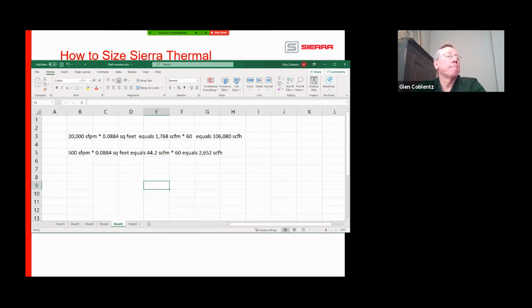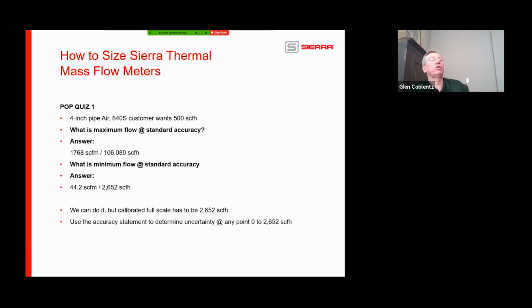Minimum flow, 500 times the area of the pipe, 44.2 SCFM, times 60 gives us this. All right, okay, great. We have that information, but let's go back up to the original question. The customer came to you saying, I've got air and I want to measure 500 standard cubic feet per hour. Is it even possible? Well, we can do it, but what do we have to do?